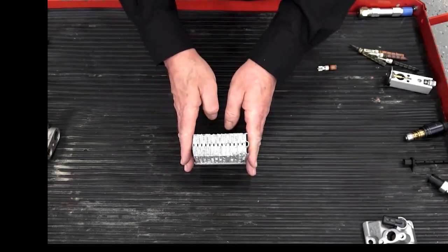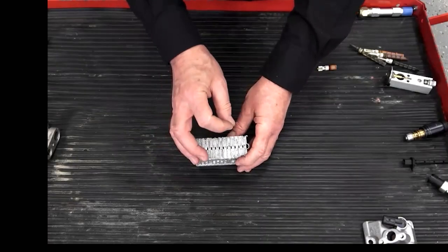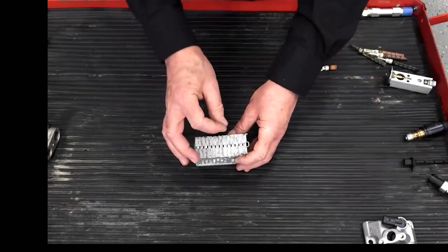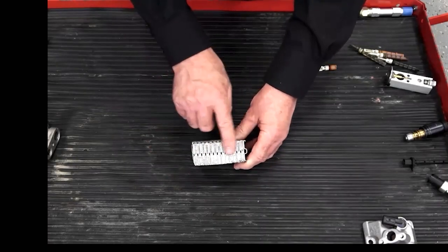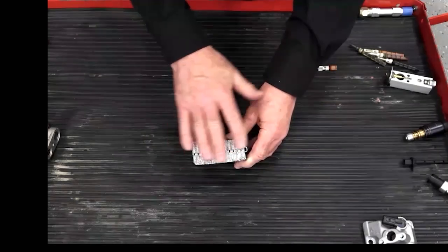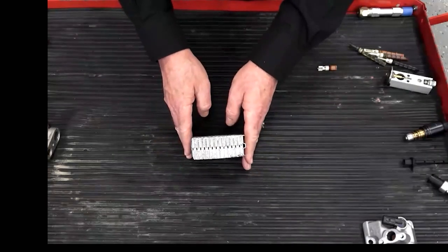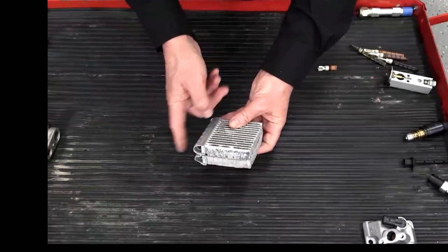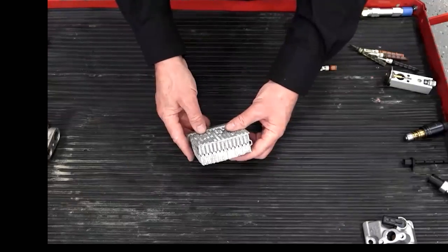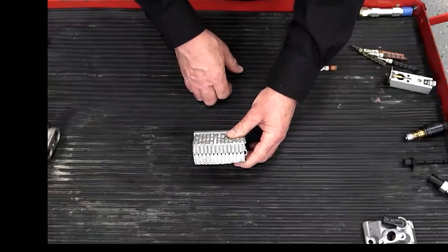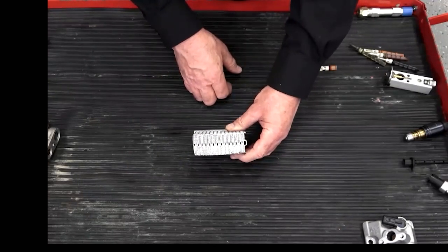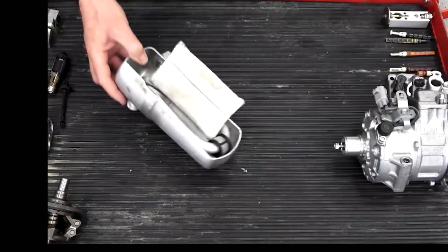And so these tubes are so small, the resistance to flow is so great, it's just impossible once you try to put flush solvent or anything of that nature in here. Plus they're often dammed at several points along the header tank. It's impossible to flush a flat tube multi-pass condenser, just FYI.